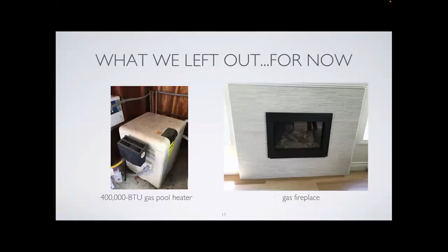On the right are the load calculations for the panel and how it would all fit on their electrical panel. In this home, the things not in scope were converting the pool heater and the gas fireplace. Adding the pool heater would require a panel upgrade, but only about a 50 amp upgrade, going from 100 amps to say 150. But if you're going to go to 150, you might as well go up to 200.